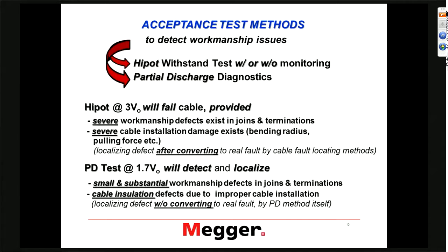What will this test reveal? It will reveal severe workmanship defects in joints and terminations, and severe cable damage from the installation. The issue — and that's why I underlined the word 'severe' — is that if there are smaller type defects in these categories, the hipot test typically will not make them fail. The way we can see that we have an issue is basically by failing the cable at that location.